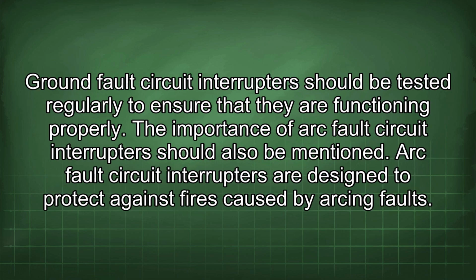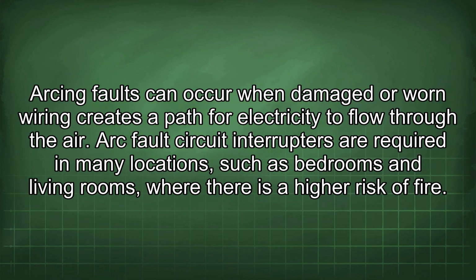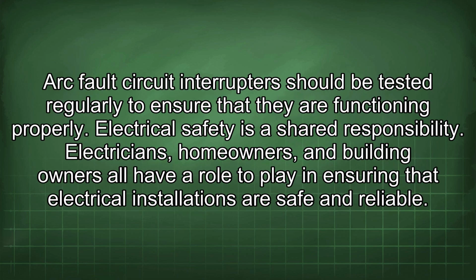Ground fault circuit interrupters should be tested regularly to ensure that they are functioning properly. The importance of arc fault circuit interrupters should also be mentioned. Arc fault circuit interrupters are designed to protect against fires caused by arcing faults. Arcing faults can occur when damaged or worn wiring creates a path for electricity to flow through the air. Arc fault circuit interrupters are required in many locations, such as bedrooms and living rooms, where there is a higher risk of fire. Arc fault circuit interrupters should be tested regularly to ensure that they are functioning properly.